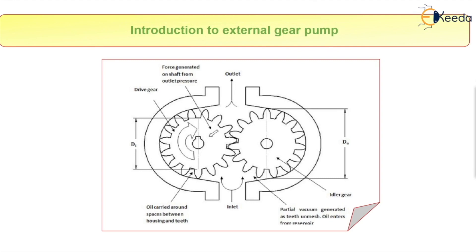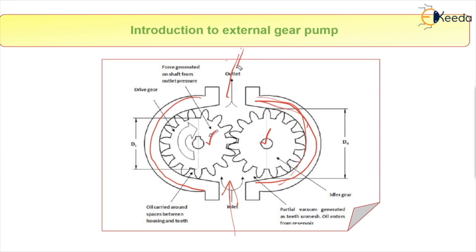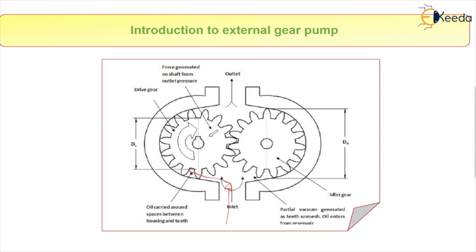Next, we discuss the external gear pump. For an external gear pump, we again need two gears — gear 1 and gear 2 — which are in contact externally, surrounded by a casing. We have an inlet on one side and an outlet on the other. The viscous fluid comes in at the inlet, moves through the spaces between the gear teeth along the casing, and is forced out at the outlet. Seals are provided so that the liquid moving toward the outlet does not go back and mix with the inlet. The direction of rotation can be reversed to change the inlet and outlet positions.